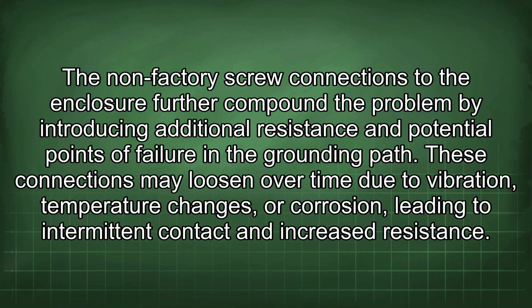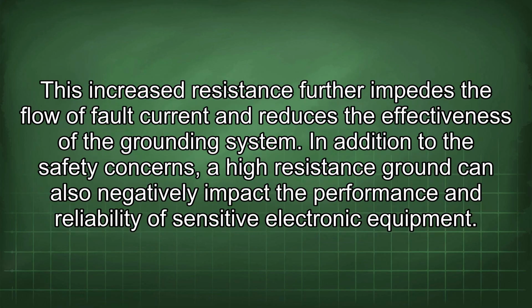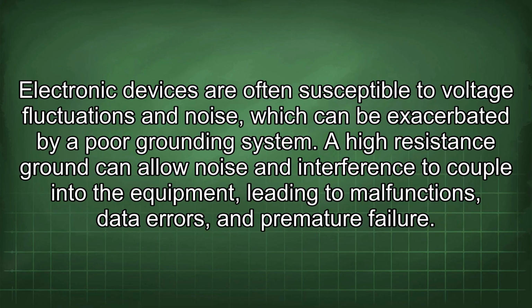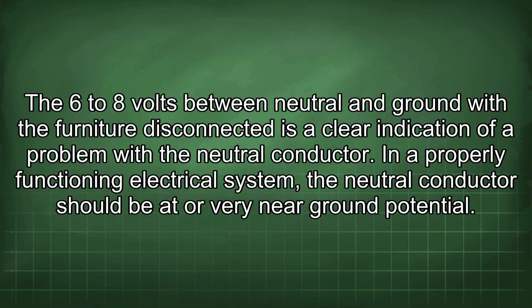The non-factory screw connections to the enclosure further compound the problem by introducing additional resistance and potential points of failure in the grounding path. These connections may loosen over time due to vibration, temperature changes, or corrosion, leading to intermittent contact and increased resistance. This increased resistance further impedes the flow of fault current and reduces the effectiveness of the grounding system. In addition to the safety concerns, a high-resistance ground can also negatively impact the performance and reliability of sensitive electronic equipment. Electronic devices are often susceptible to voltage fluctuations and noise, which can be exacerbated by a poor grounding system. A high-resistance ground can allow noise and interference to couple into the equipment, leading to malfunctions, data errors, and premature failure. The 6 to 8 volts between neutral and ground with the furniture disconnected is a clear indication of a problem with the neutral conductor. In a properly functioning electrical system, the neutral conductor should be at or very near ground potential.